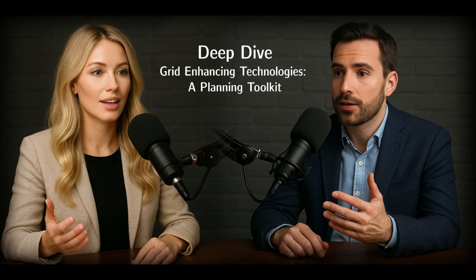Dynamic line ratings, DLR. You said it's often the first step. Yeah, it's often considered the first logical step, mainly because of those typically very high benefit-cost ratios we talked about, and the implementation risk is generally quite low. It's proven tech. So what are the technical fundamentals? What's wrong with the old static ratings?